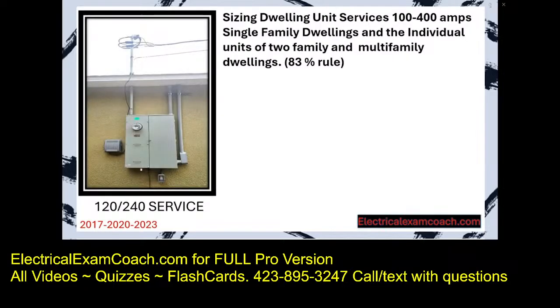Now let's learn how to size dwelling unit services and feeders in between 100 and 400 amps. This applies to single-family dwelling units and the individual units of two-family and multifamily dwelling units. And it's affectionately called the 83% rule. The next few slides are very dense, so I want you to slow down, take your time, watch it as many times as you need, but I know that you can do it. Keep up the great work.